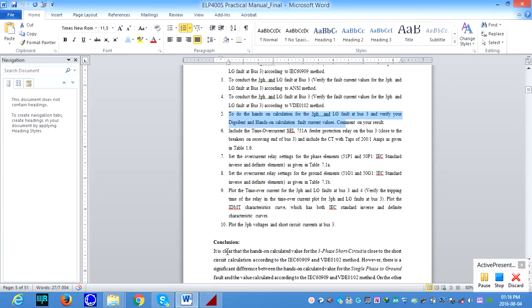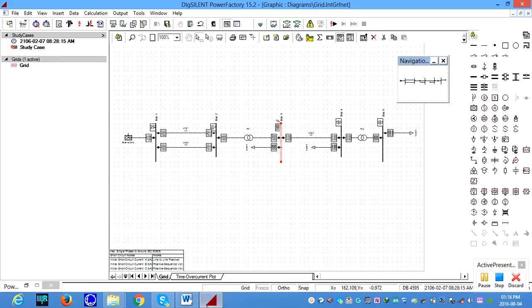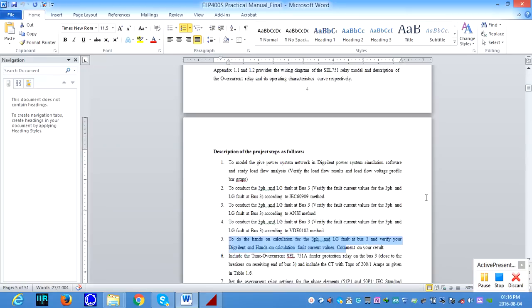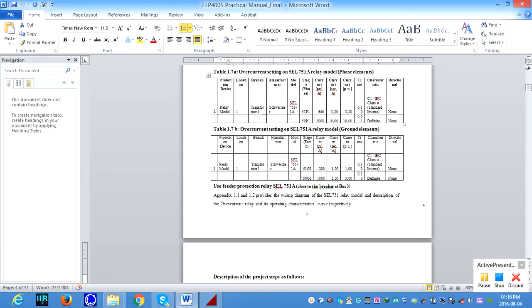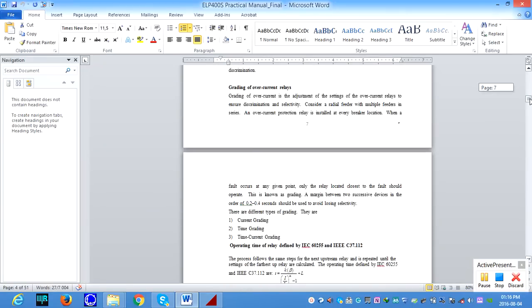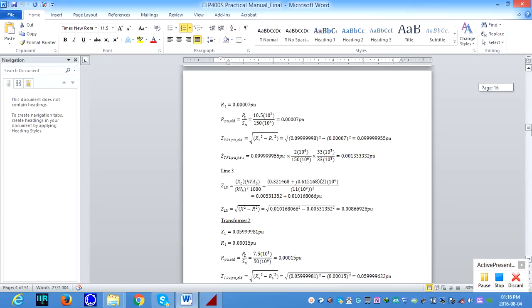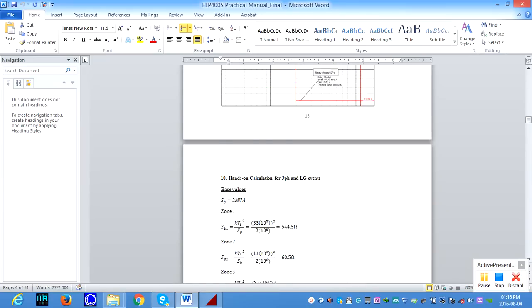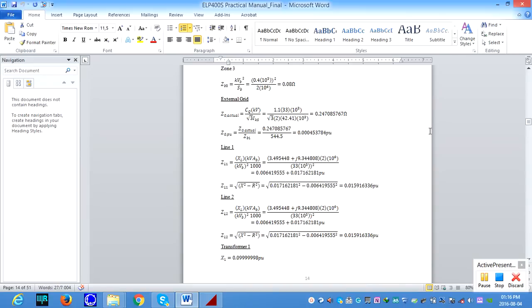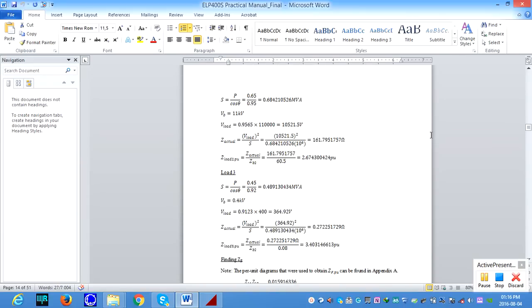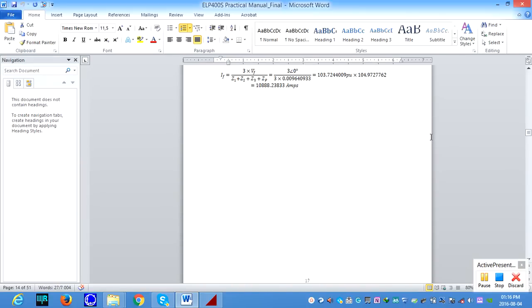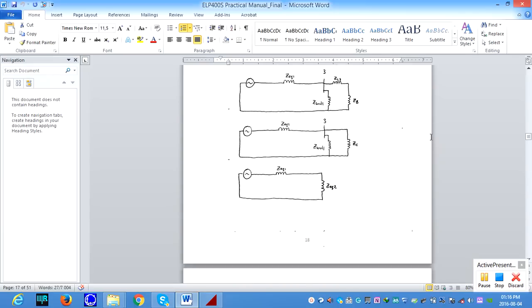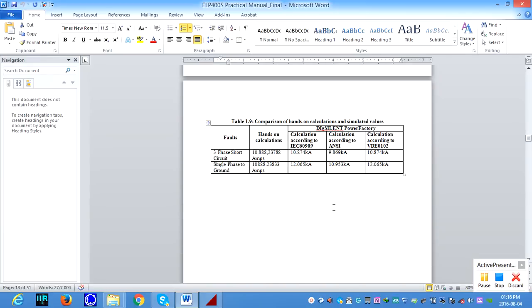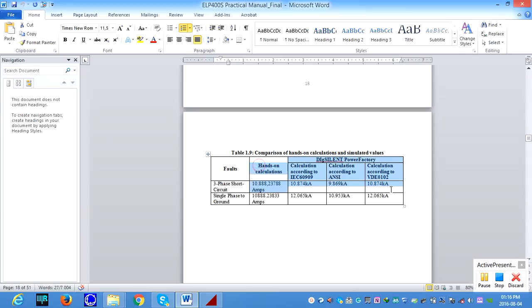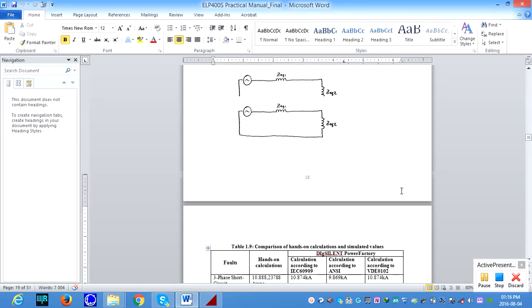Okay, as part of your chapter 1, you need to do the hands-on calculation to validate your DIgSILENT results. That is part of the memo, but you need to work it out, and I will show the snapshot. So you need to do the hands-on calculations in order to validate the fault current values, using the reduced equivalent diagram. And finally, you need to compare the results of the ANSI method with the IEC method and the VDE method.